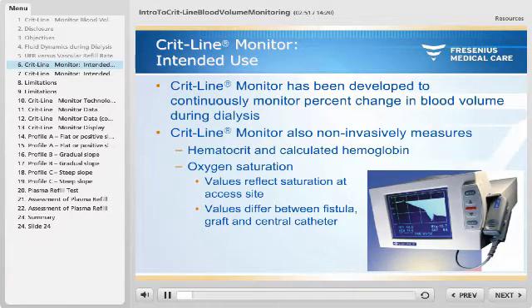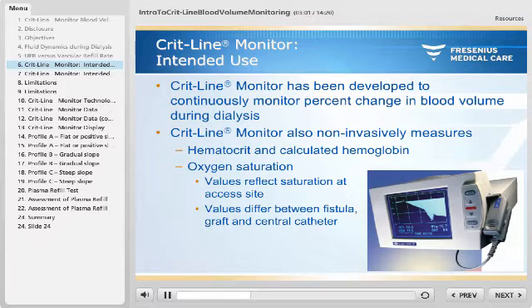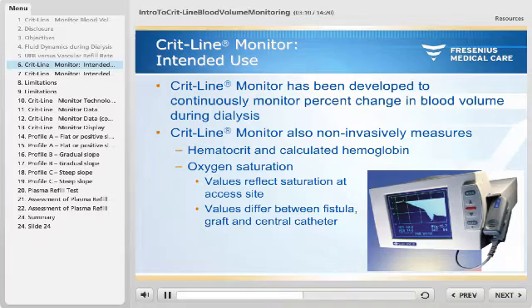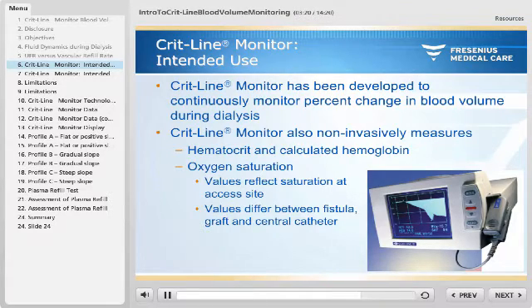The Crit-Line monitor has been developed to continuously monitor percent change in blood volume during dialysis. It also non-invasively measures hematocrit and calculated hemoglobin, as well as oxygen saturation. It is important to remember that normal values for a fistula or graft can differ from a central catheter. Given this variation, standardized treatment recommendations based on certain oxygen saturation values are not available.